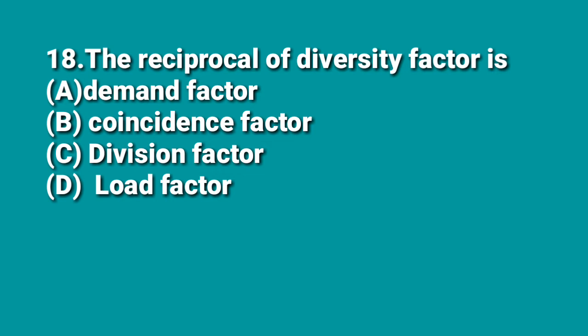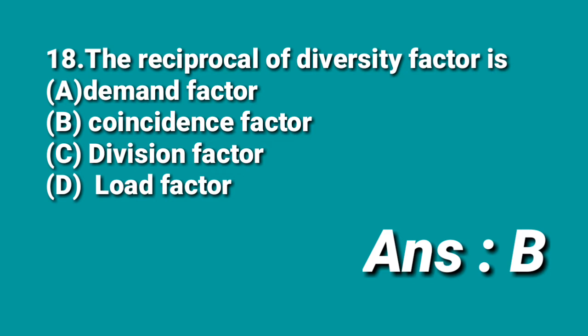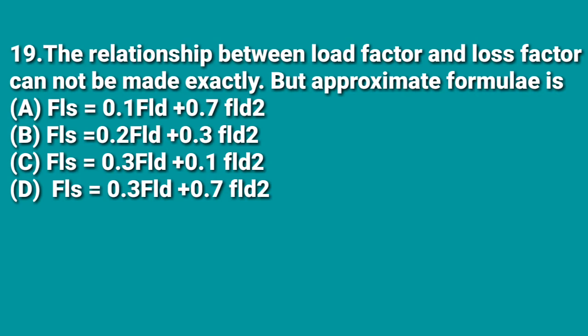The next question: the reciprocal of diversity factor is — A: demand factor, B: coincidence factor, C: division factor, D: load factor. The diversity factor is defined as the ratio of sum of individual maximum demands to the maximum demand; its reciprocal is the coincidence factor, so B is the correct answer. The relationship between load factor and loss factor cannot be made exactly, but the approximate formula is: Loss factor = 0.3·FLD + 0.7·FLD², which is answer D.